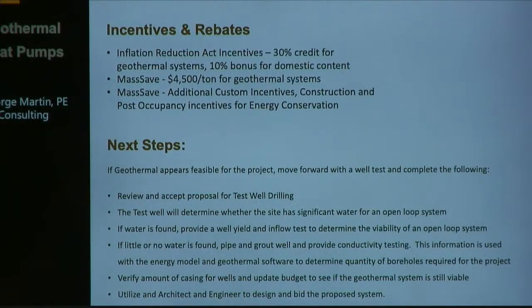Usually, for example, after 15 years you're going to have to replace the well pump, just like any residential well pump—it does fail, but so do other components. There are also pumps required for the internal hydraulic system that can fail too. The main thing is water quality, making sure you have the right injection capacity, and that heat exchangers don't foul up over time. With bad water quality, heat exchangers can foul, which just means you have to clean them. We've had sites that haven't cleaned them for 15 years and they're fine.